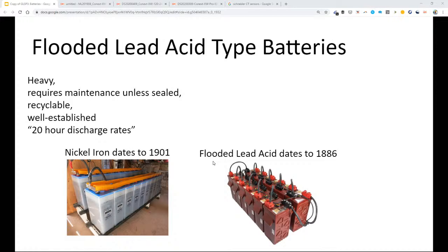If you do a battery bank, flooded lead acid for the whole house, you might say, well, let's only do a day of storage or a half day of storage. But the variable load on a house is tremendous. So even if you have the right sized inverter and the right sized battery, if you're blowing past the peak load discharge rate of a C6 or a C5, it's not going to have that 8 hours of storage - it's going to have less than that.